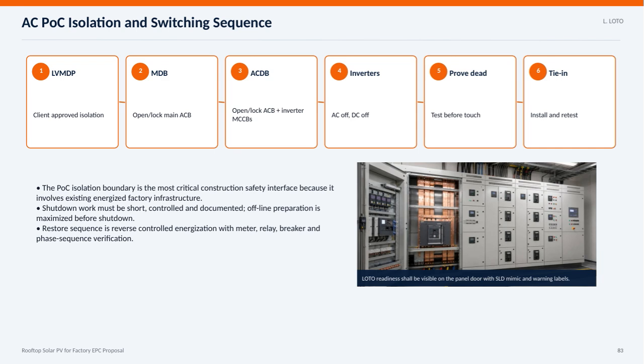The restore sequence follows a carefully managed process with verification of meters, relays, breakers, and phase sequences to ensure everything is safe and functional. Additionally, lockout-tagout, or LOTO, readiness must be clearly visible on the panel doors, featuring single-line diagram mimics and warning labels. This visibility helps everyone involved recognize the safety status at a glance before proceeding.